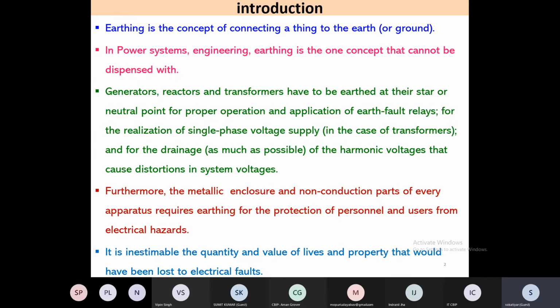The person who may come into contact with this electrical equipment will not get electrocuted. So in all electrical equipment, there are two purposes of grounding. One is human safety, so that somebody should not get electrocuted, and another is the protection of the equipment. It is inestimable, the quantity and value of the lives and property that would have been lost to electrical faults.